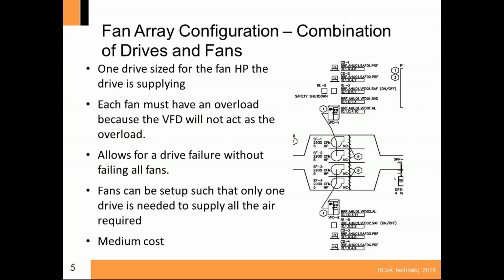This is a medium cost. You're going to have overloads on each one of the motors, and then you have the 2 drives, so all you're really saving is the cost of a drive. We could have put 4 drives on this one and probably done the same thing, sizing up the fans. You'll see that sometimes in hospitals where they want to do a 2N redundancy or N+1, and you'll just see that drive setup.